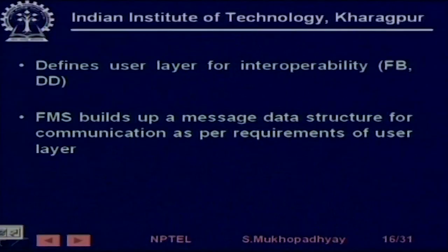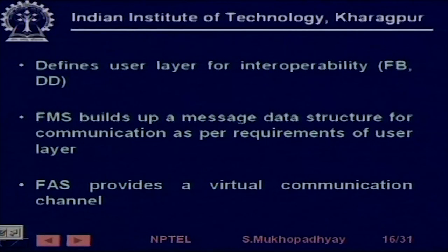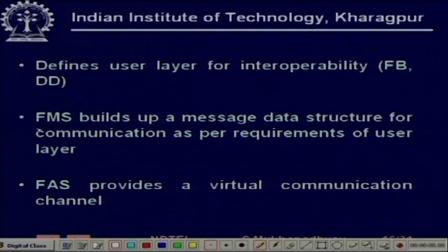The Fieldbus message specification: the user layer just abstractly gives, maybe an analog input block simply generates a value. This particular temperature signal has to go to the PID controller, it says. Now, for transmitting that to the PID controller, this has to be made into a message, and then the message has to be configured into a packet, and then it has to be sent after all the addressing, etc. So the Fieldbus message specification builds up the message data structure for communication as per requirements.